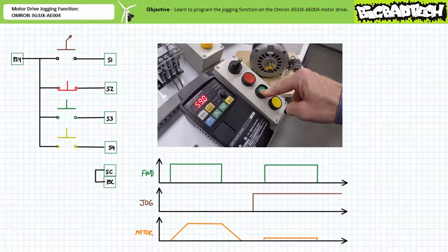When an operator opens input 3, the motor drive decreases applied voltage and excitation frequency. The motor decelerates and turns off. Note, in full speed mode, the motor drive applies full voltage and current at maximum frequency during the constant speed run state, as we'd expect.